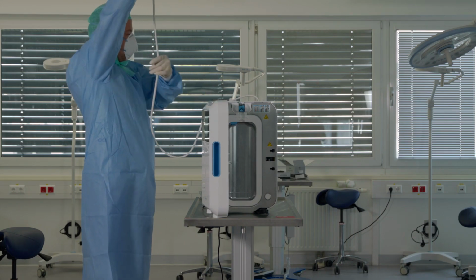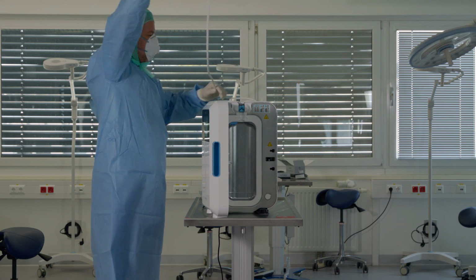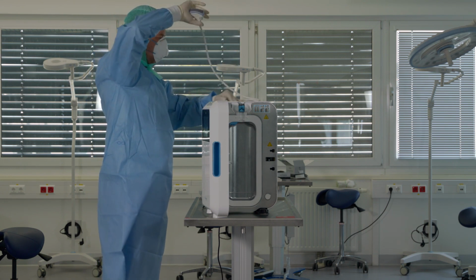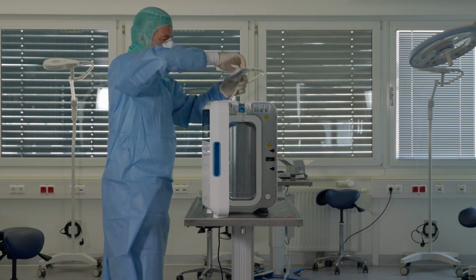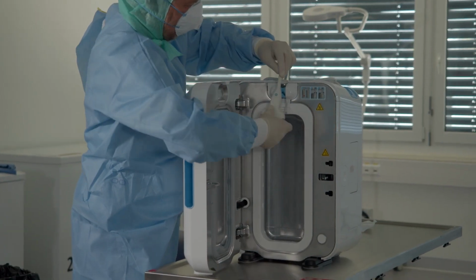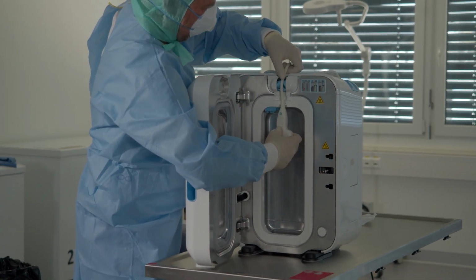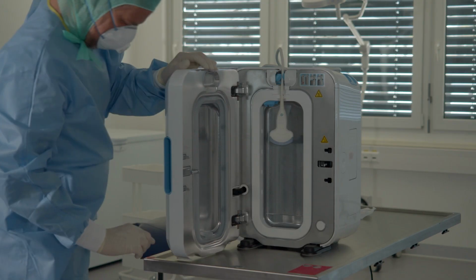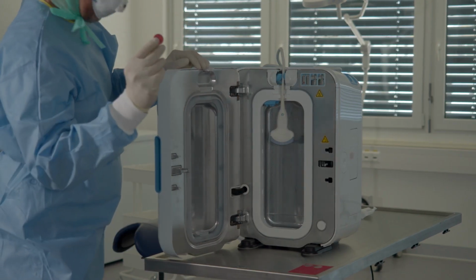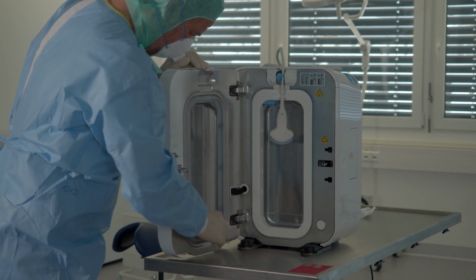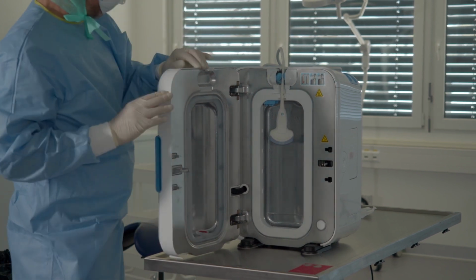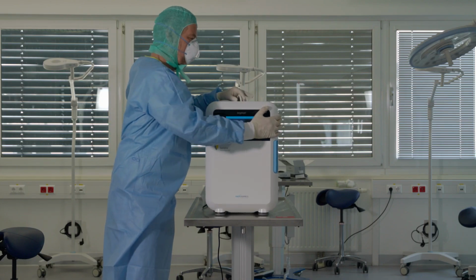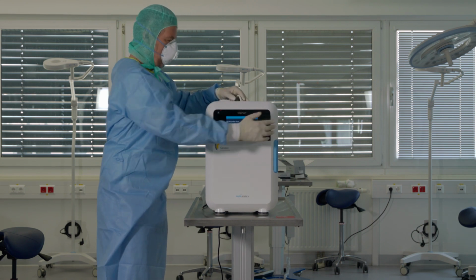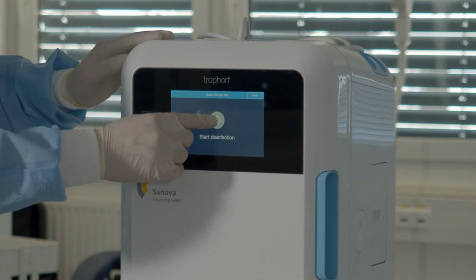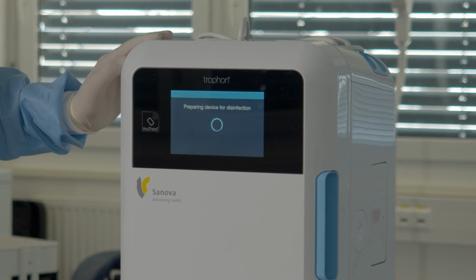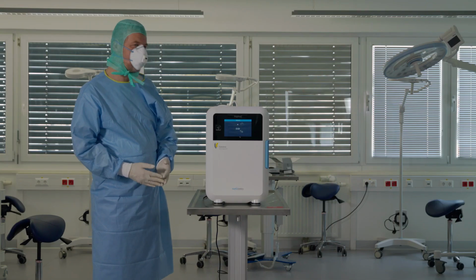Special systems are available for quick and easy high-level disinfection. Such systems use a vaporized hydrogen peroxide solution, which has been shown to be highly effective against pathogens. After examining a patient and roughly cleaning the probe, place it in the disinfection system. An indicator, placed into the system along with the probe, provides evidence that the disinfection process is complete. Accommodating a wide variety of probes, the system produces results within just a few minutes.